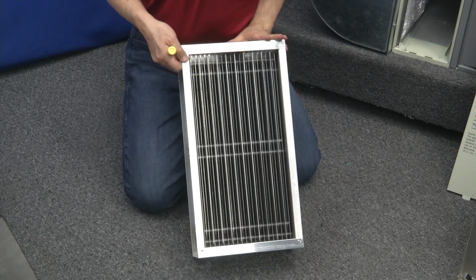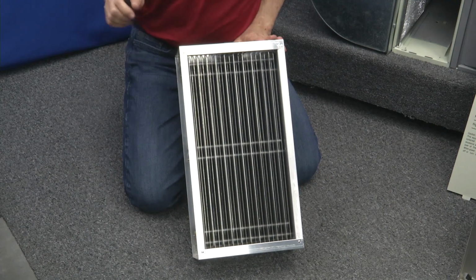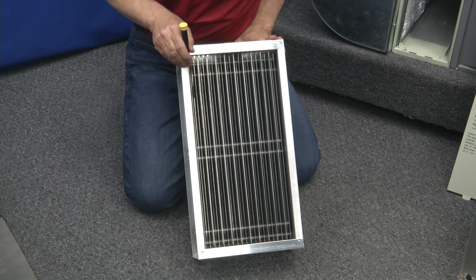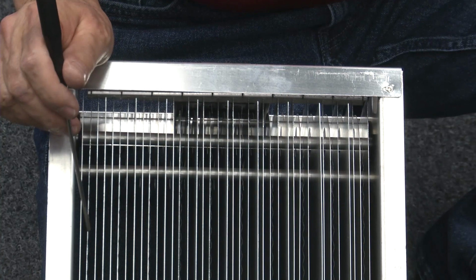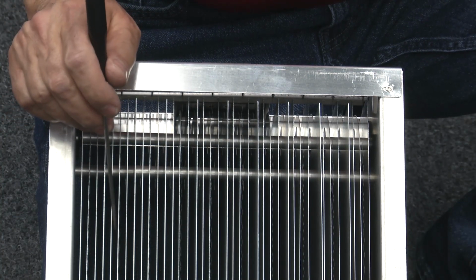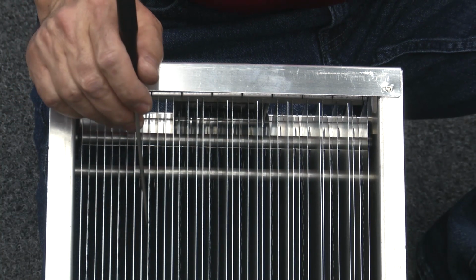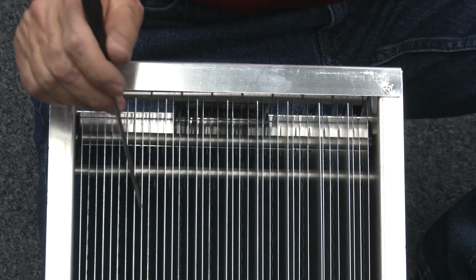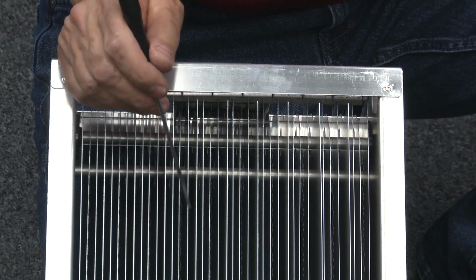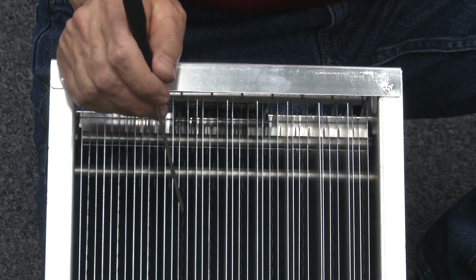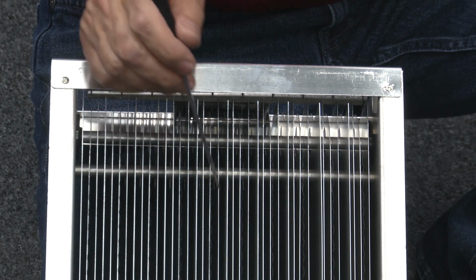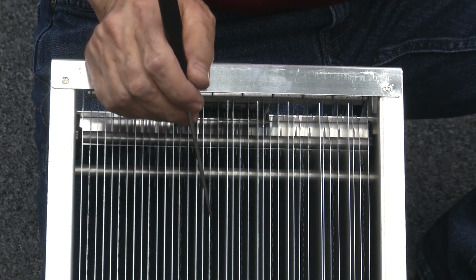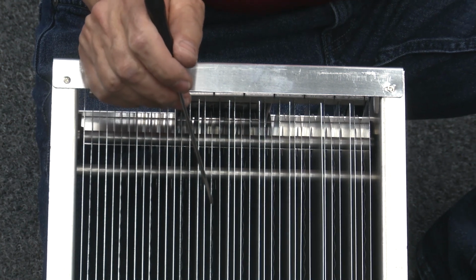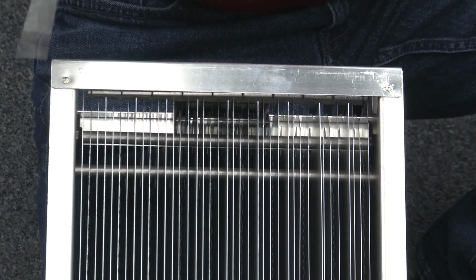This side has the ionizing wires in it, so we're making sure there's a wire between each of these spaces, and there is. They're wavy, very thin wires that look like piano wires, called ionizing wires, and they run between each section. Sometimes one of these wires will break and flop around, or part of it gets stuck between the plates, shorting it out.